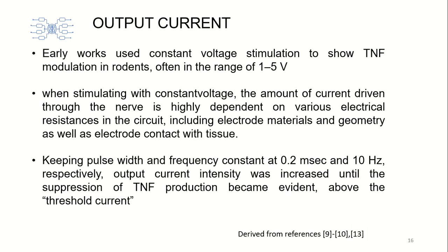The various electrode geometries employed in the tests were probably a factor in the absolute difference between the two species. There was no discernible loss of function across a range of intensities above the threshold current, which is significant for stimulation design. Constant current of 0.75 to 1 milliampere, or even 2 to 3 milliampere, was used in numerous subsequent mouse trials to ensure the therapeutic threshold was exceeded.